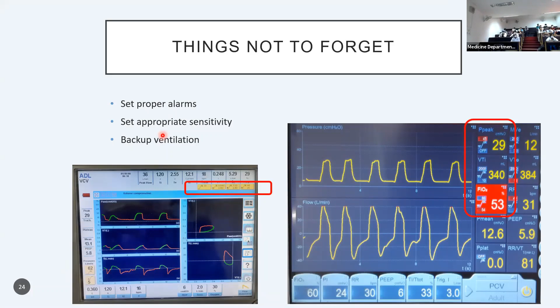Second, set appropriate trigger sensitivity. And third, set backup ventilation. In case you have a PSV mode, if an intubated patient is on PSV mode, don't forget to set up a backup ventilation. Many ventilators don't allow you to set a PSV mode unless you have set up backup ventilation.